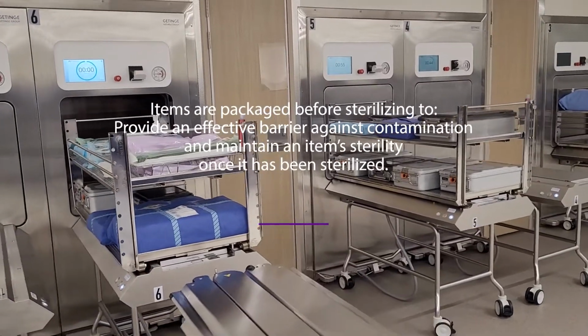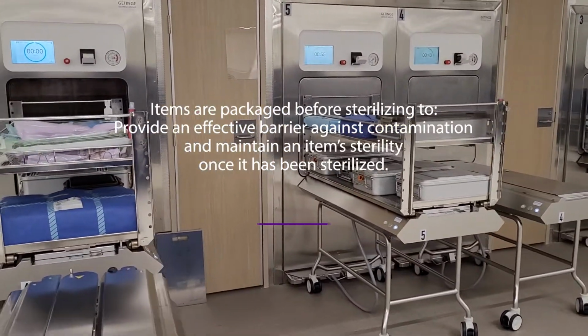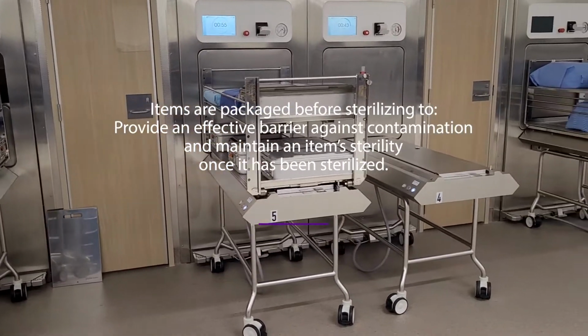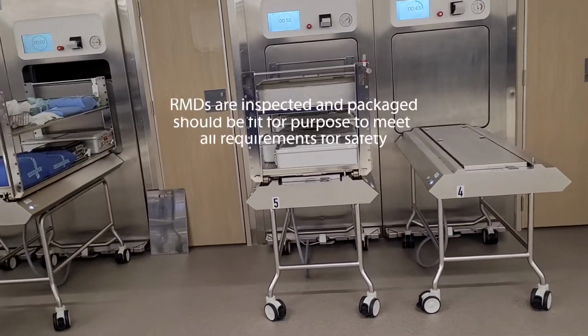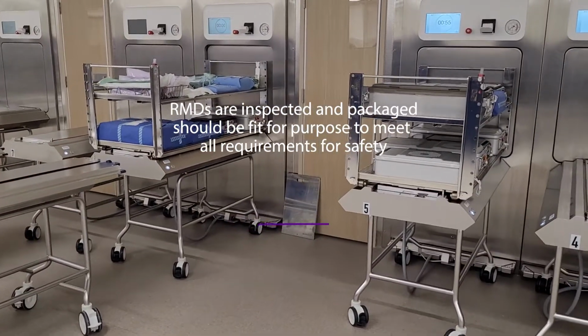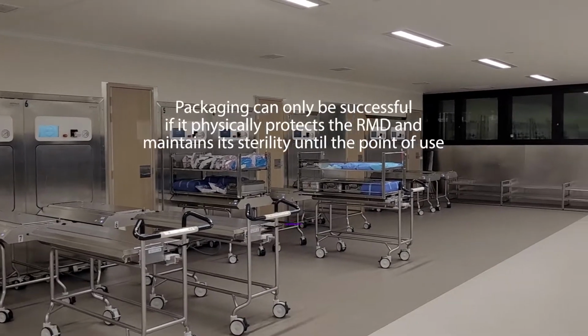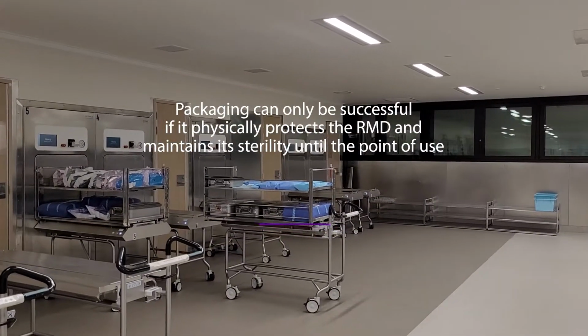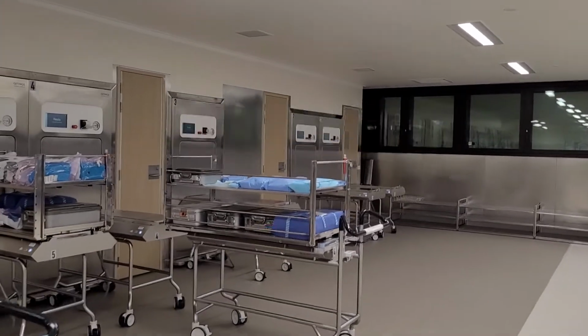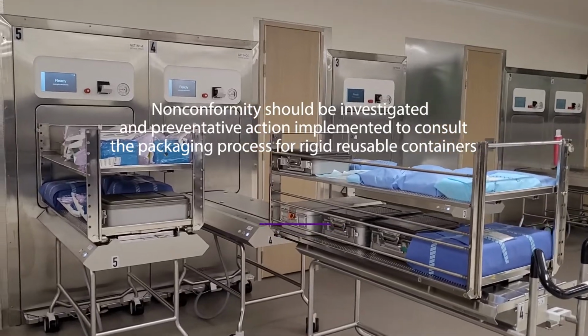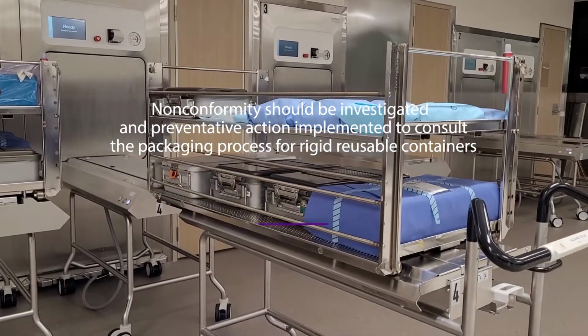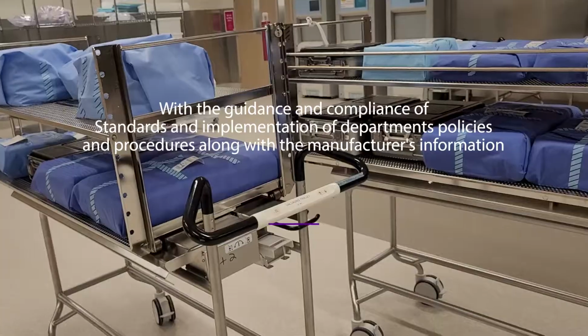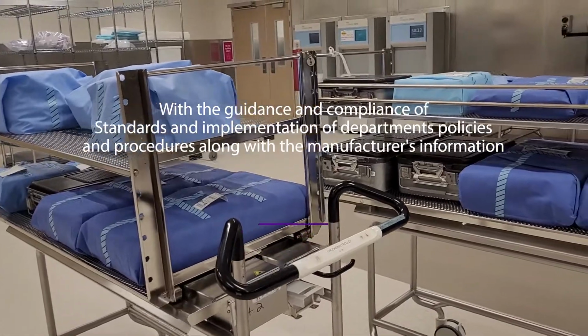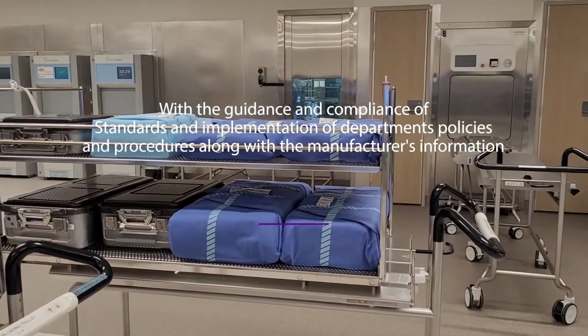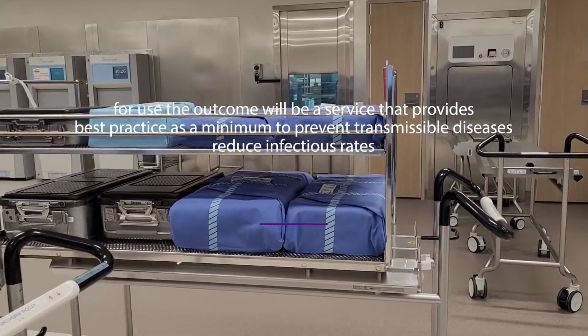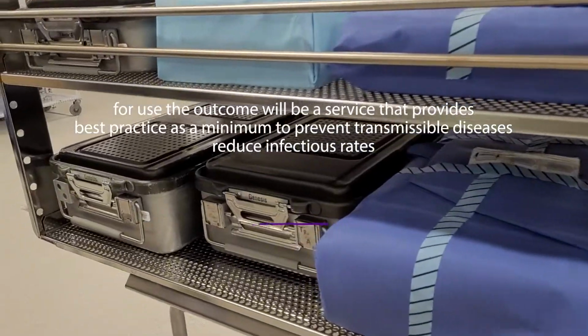Packaging summary. Items are packaged before sterilizing to provide an effective barrier against contamination and maintain an item's sterility once it has been sterilized. RMDs that are inspected and packaged should be fit for purpose to meet all requirements for safety. Packaging can only be successful if it physically protects the RMDs and maintains their sterility until the point of use. Non-conformity should be investigated and preventative action implemented to improve the packaging process for rigid reusable containers. With the guidance and compliance of standards and implementation of the department's policies and procedures, along with the manufacturer's information for use, the outcome will be a service that provides best practice as a minimum to prevent transmissible diseases and reduce infection rates.